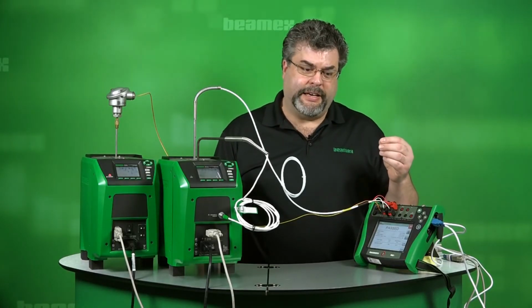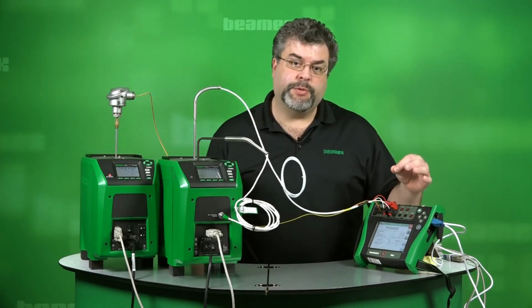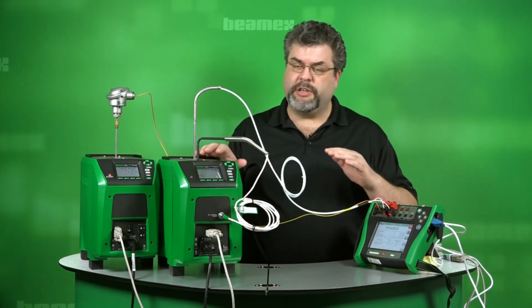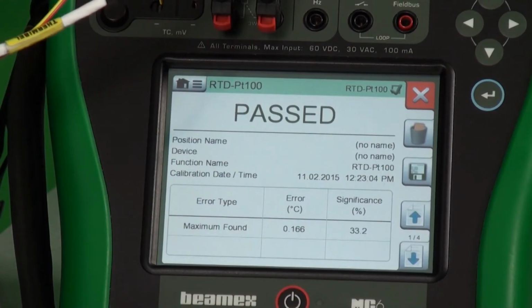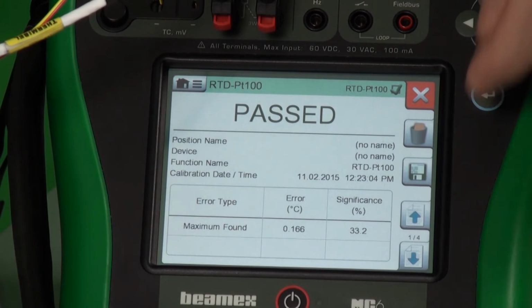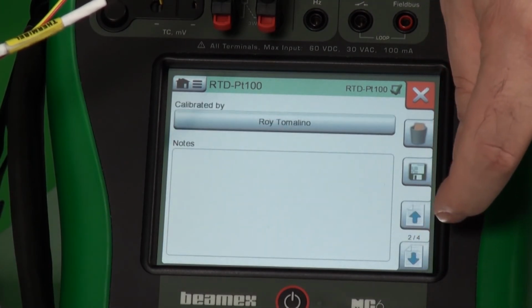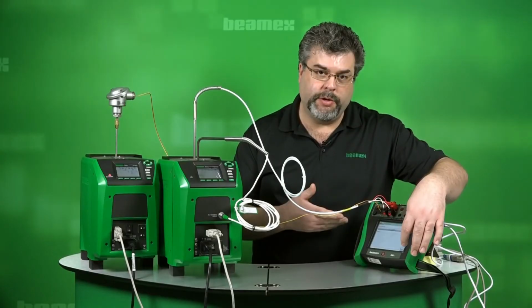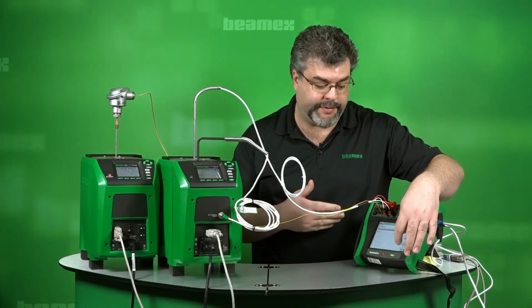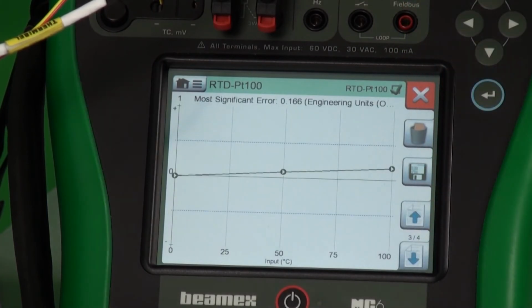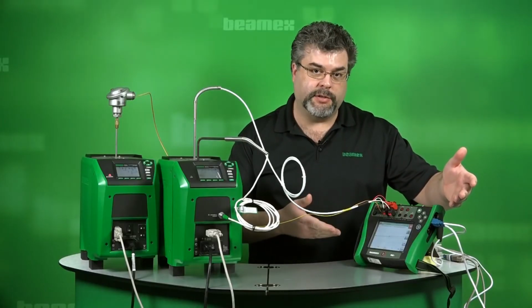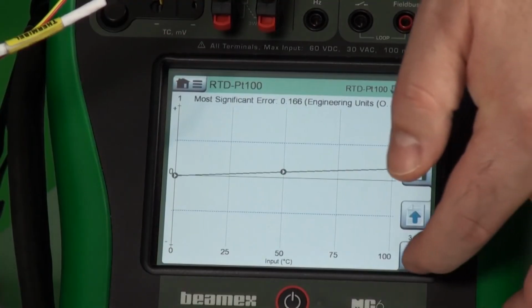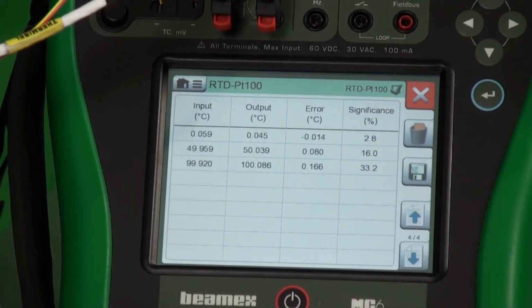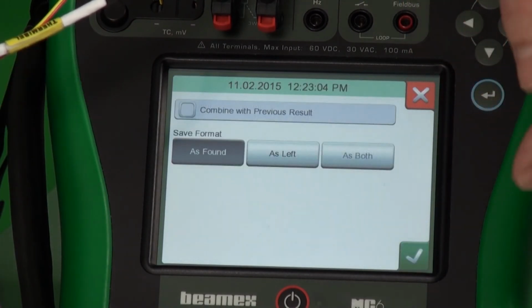Remember, we're doing a grouped calibration. So we're getting the test results from the very first test that we did, which was the RTD from this dry block. Notice on the top it says RTD. So it says passed. It gives us a summary of what the test was, but we can go get further detail. We can enter in notes about the calibration, and this will pop up on the calibration certificate after the fact. We see the graph itself, and we can see the RTD tracked nicely. It was well within our limits, and this would be put back into service with a stamp of approval. And then we have the raw data. Let me save this. We'll save it as found.